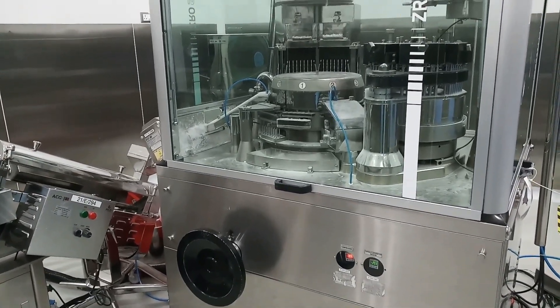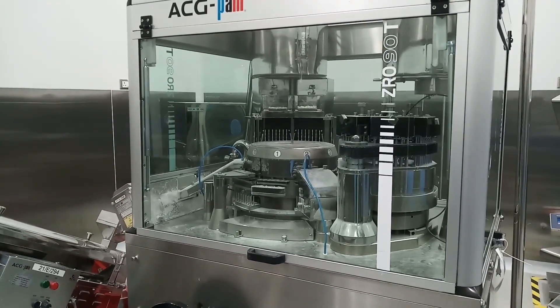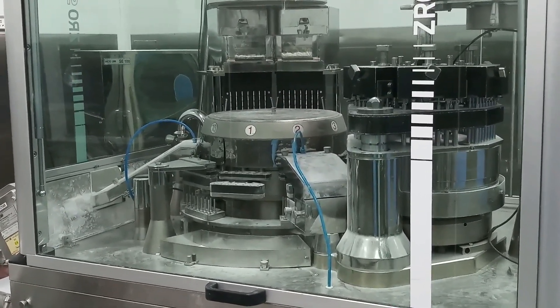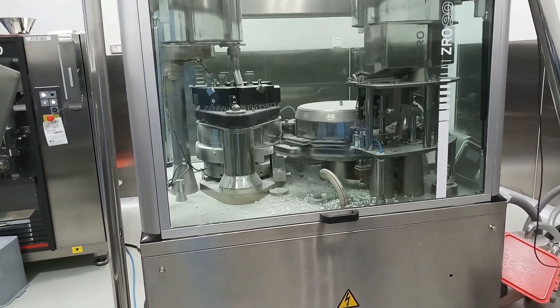The AF90T is a high capacity fully automatic capsule filling machine that can fill a large variety of powder formulations into hard gelatine capsules. The machine is formulation friendly and uses a tamping process to form a slug which is inserted into the empty capsule. A pellet filling device is available as an optional attachment.